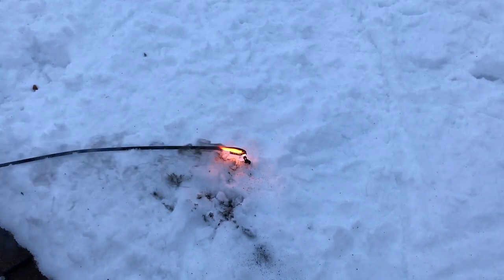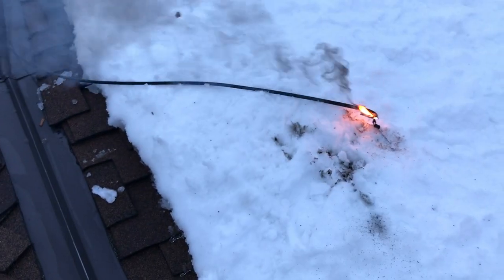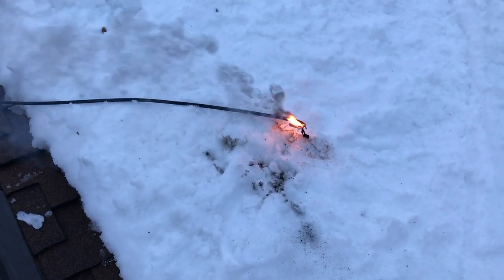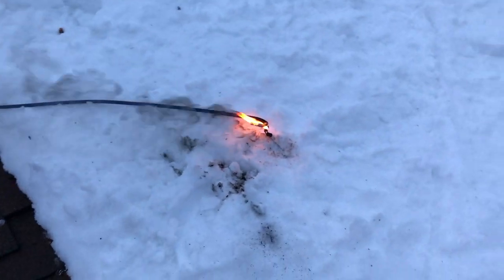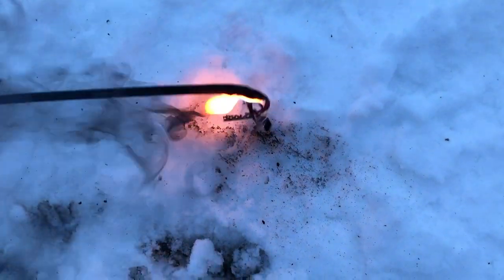This heat cable project was in Eden, Utah, and we were lucky enough to be on site to catch the footage and see firsthand what it's like when heat cable catches on fire. You would think that this would have tripped the breaker, but obviously it kept burning. They didn't have the right type of breaker in the panel or protection on the system.